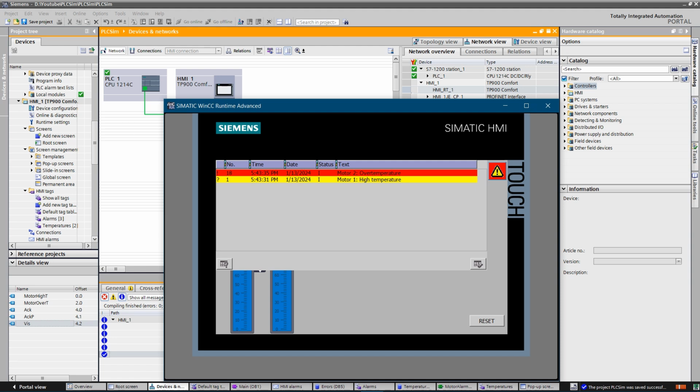A warning is activated when a motor reaches a temperature of 70 degrees Celsius. On getting a warning, the operator also gets a message on actions that need to be taken into account. The motor will not be stopped when a warning occurs.